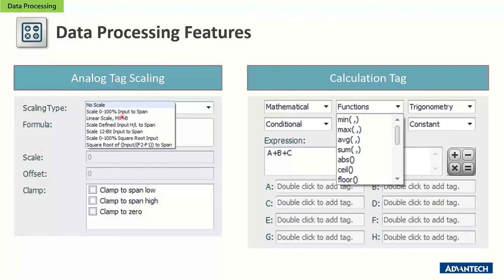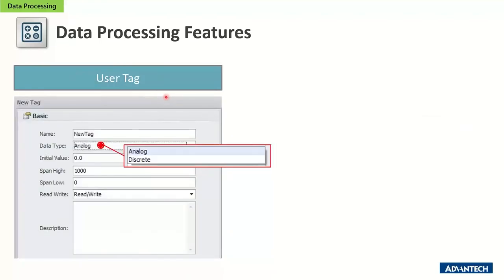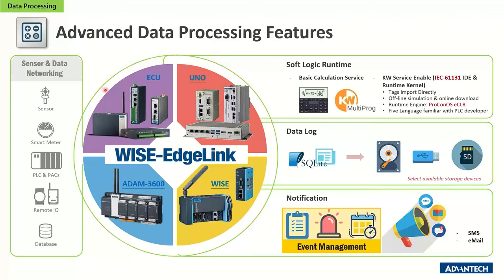The calculation tag lets you define formulas such as A + B + C, where A, B, and C can be temperature values from different sensors. You can use functions including min, max, average, sum, and conditional logic. User tags act as internal tags, mainly for set points — you can define initial analog or discrete values at device boot-up. For advanced data processing in EdgeLink, there's also soft logic, a logic program that you configure and run inside EdgeLink using the IEC 61131-3 standard with KW MultiProg software.